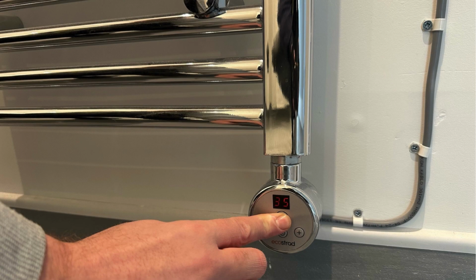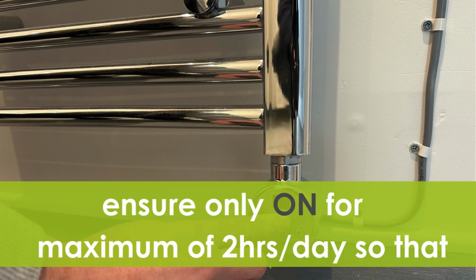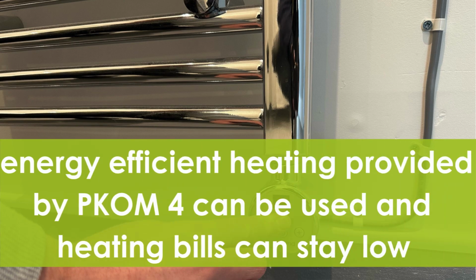As a part of the heating plan, there is also a heated towel rail fitted into the bathrooms. These are meant to be used for a couple of hours a day during the winter, just on a timer or a boost drying function. But these shouldn't be left on all day, every day during the winter, as you do not want it to become a part of the primary heating and actually overtake the PKOM's drive for the heating system.